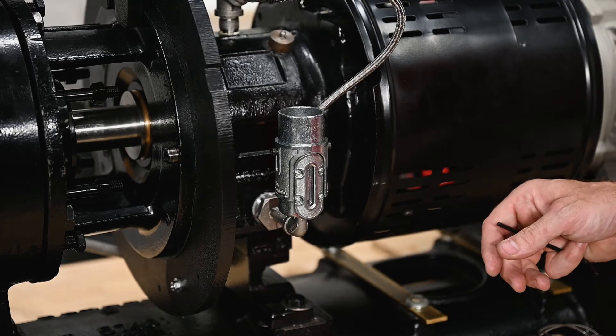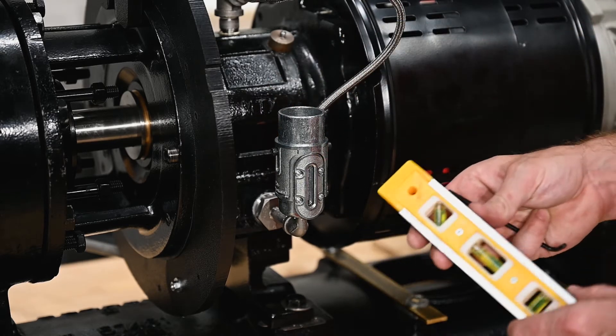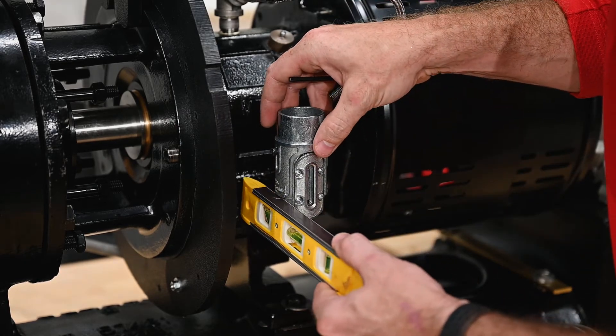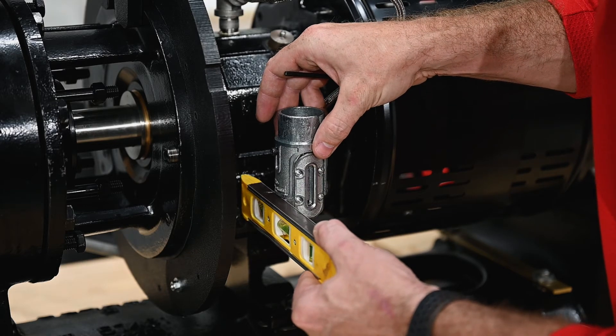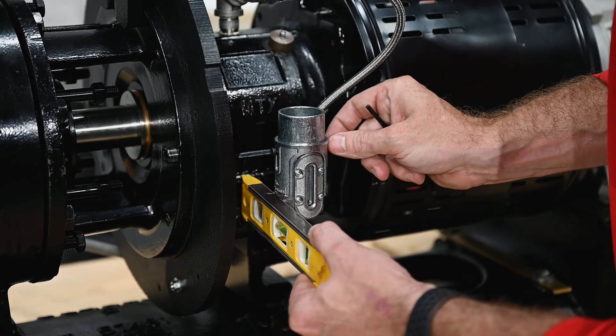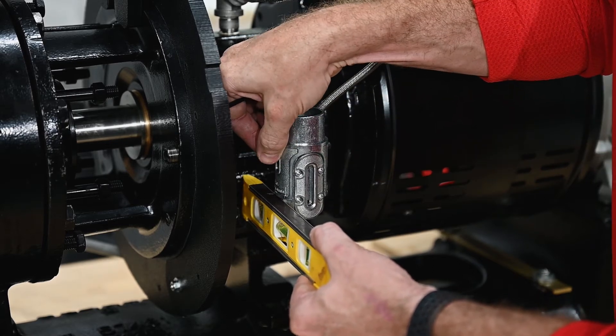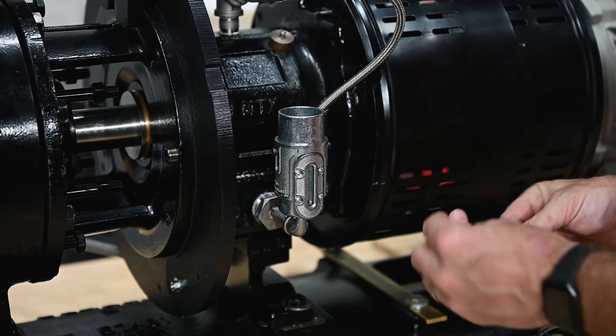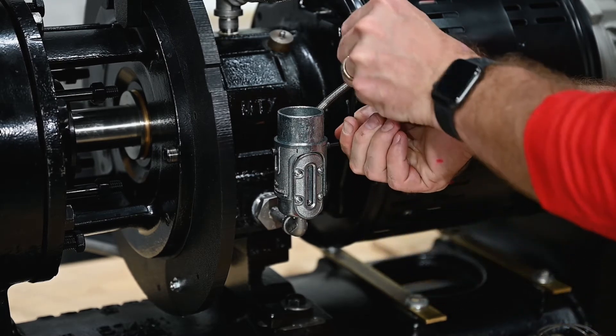Next we're going to set our lower collar assembly to the desired oil level. We'll use a level and butt that up against the bottom of the collar, getting it directly to the desired level on the pump housing, then adjust the Allen head screws to tighten that collar into position. This is going to set the proper oil level inside of the oiler.